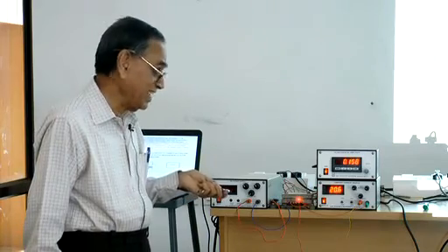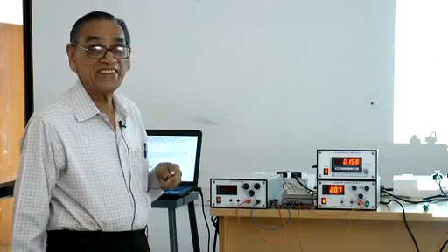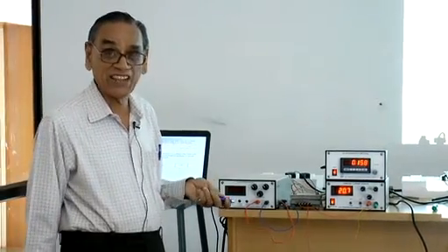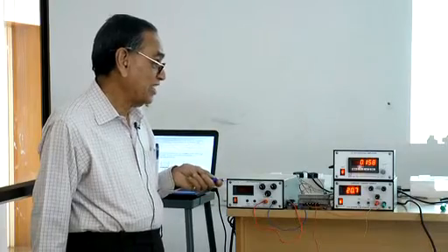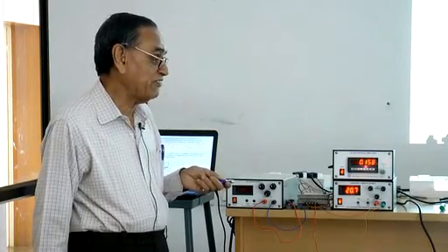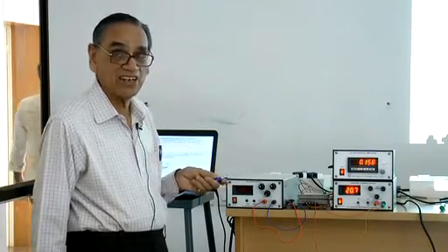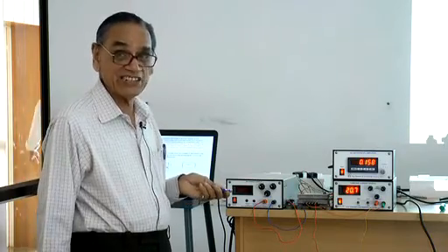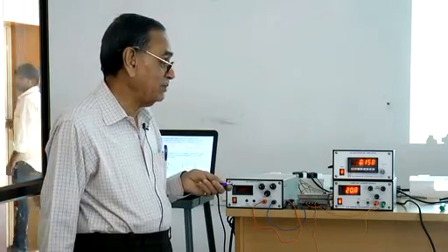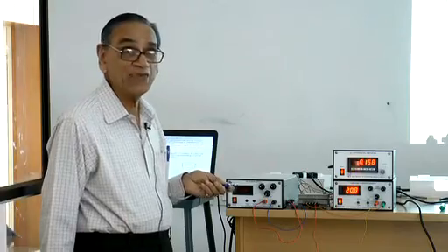The sample here is not nitinol. It is a nickel copper alloy which has a low resistance, and so the voltage is 158 microvolt. For the nitinol sample, the voltage will be about 5 millivolts.